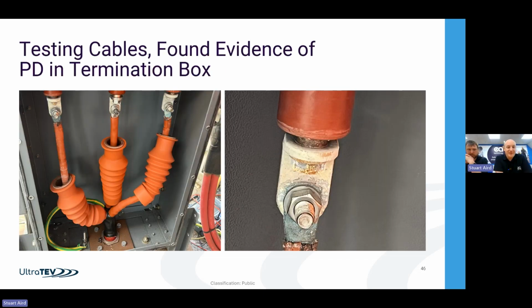And this last little picture is one that I've added. We were doing a cable testing job and we energized the cable. We got up to half the operating voltage, and the tan delta measurement literally went off the scale. So we stopped the test at that point and opened up the terminations of the cable and found this quite advanced partial discharge. The cable was out of service when we got to site, so we couldn't do a handheld partial discharge survey. So sometimes cable testing can also find problems in your cable terminations as well.